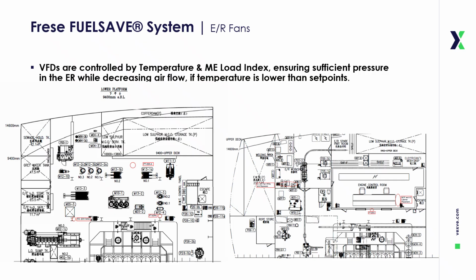From a signal perspective, the system provides analog feedback of fan speed and power consumption, digital alarms for deviations or drive faults, and full integration with the vessel's automation and monitoring system, allowing operators to track performance in real time. By applying this closed-loop control strategy, FuelSave not only reduces fan energy consumption, but also minimizes noise, extends equipment lifetime, and contributes to the overall fuel-saving potential of the vessel.